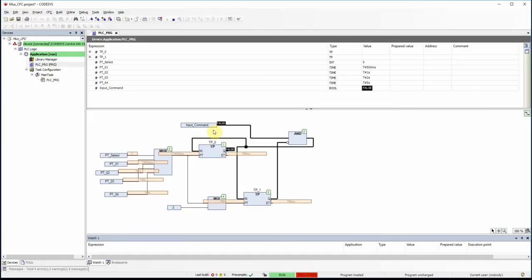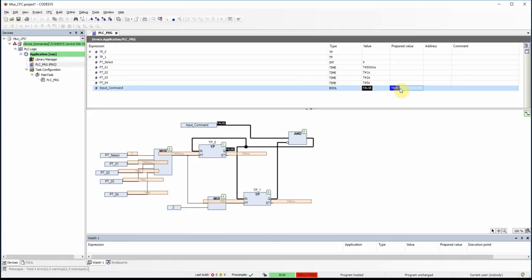Since the command input is false we don't have any pulse. I click on the prepared value, press F7 and Alt+F7 to force it, and now we have the output of the first timer showing pulses — 500 milliseconds true, 500 milliseconds false.